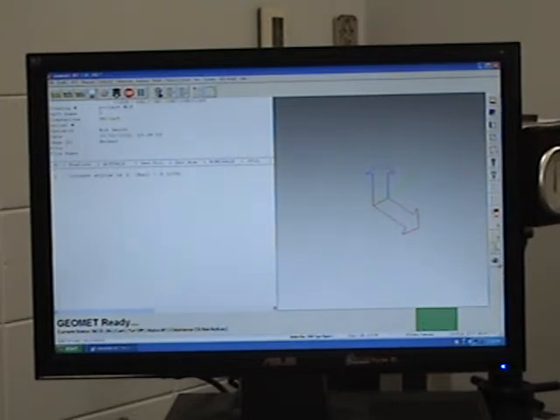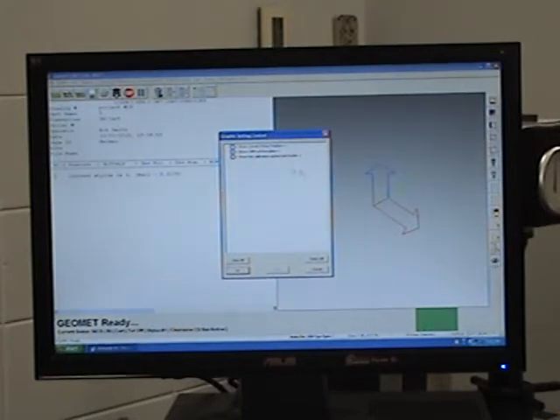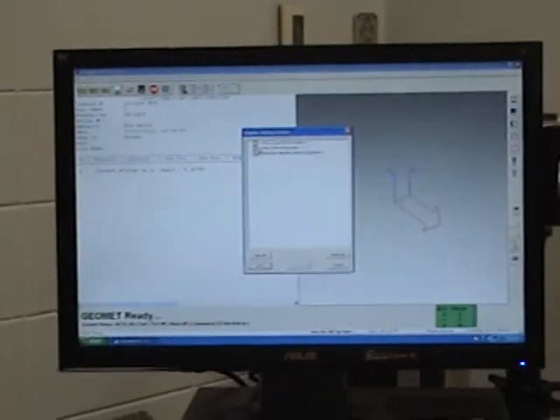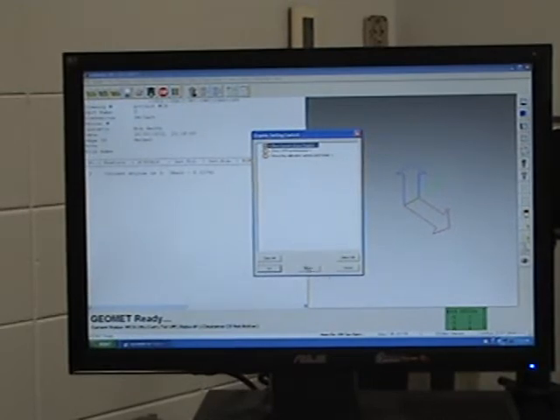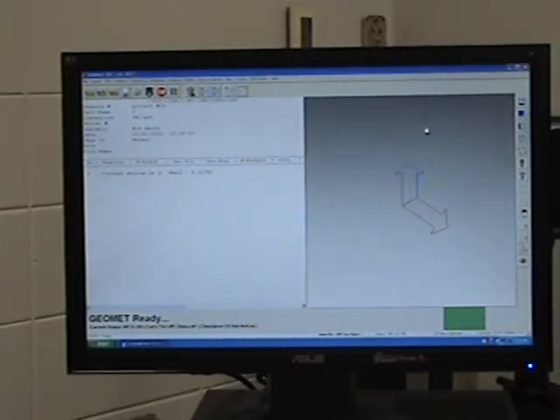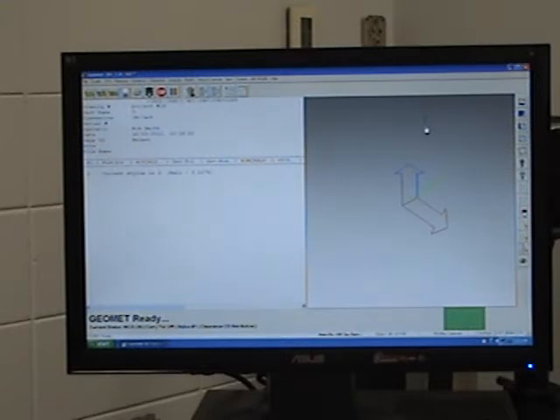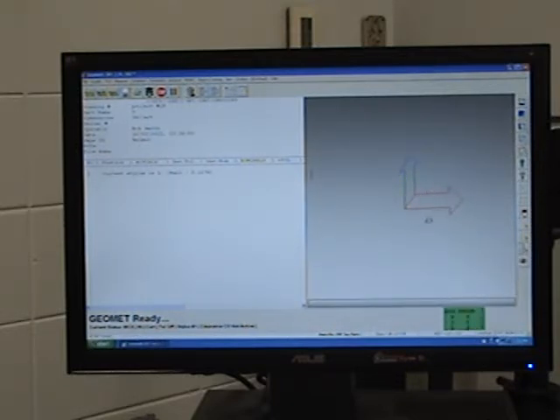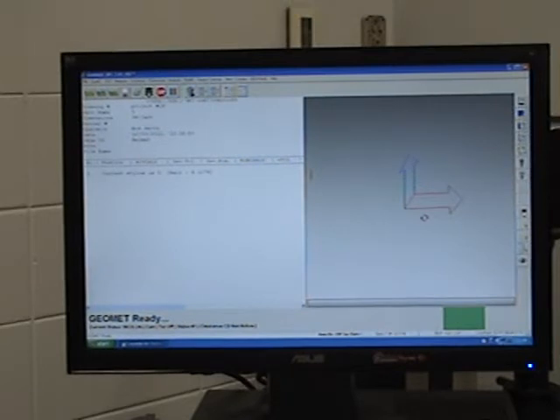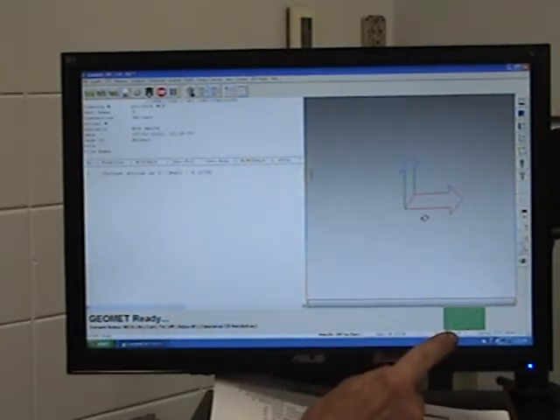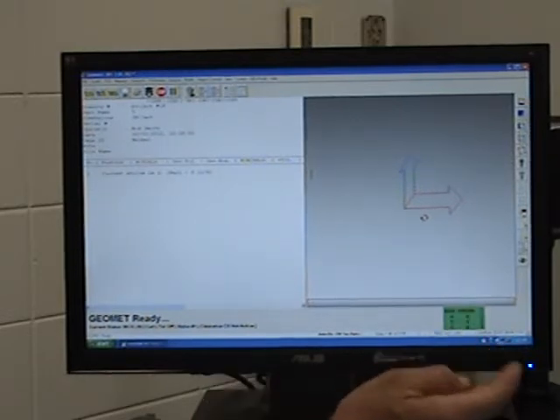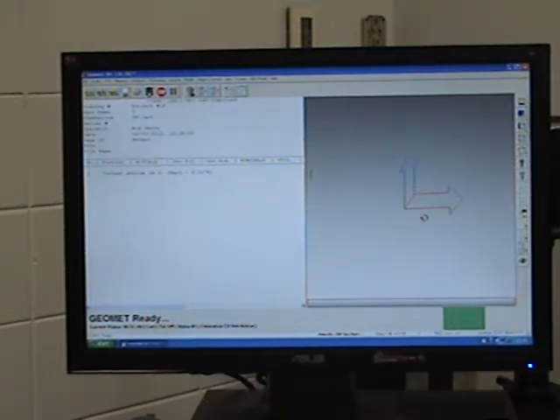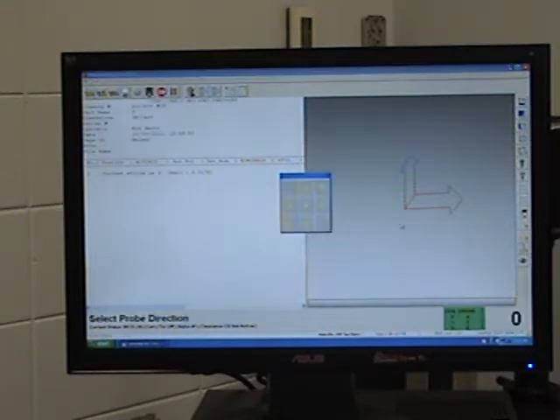So what I want to see on the screen, I'm going to click on the little eyeball here, and I'm going to click on stylus. We want to see the stylus, and there it is right there. So we're going to do a part coordinate system. We can click on this fifth icon down, and we can move this around. This is now the machine coordinate system, and it knows where the machine is at. But you notice the flashing axis origin down here, the PCS setup is not complete.